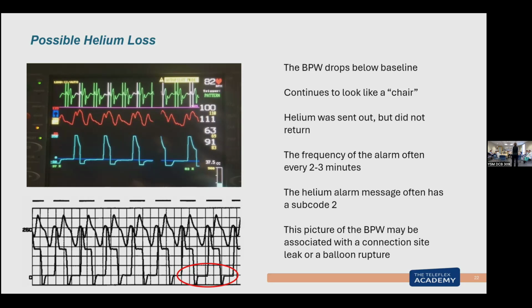If I don't get it back, this is something more than a pump issue. This is not a pump issue. This is a patient side issue, and I've got to figure out why that is. So with helium loss 2, a lot of times you won't see blood in the tube. But the pump keeps alarming every 2 to 3 minutes. I hate that. Connection site or hole in the balloon. We can actually do an internal leak test with the balloon in the patient.